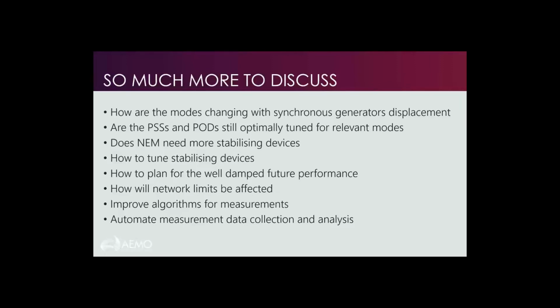On stabilizers again, can a reduction in inertia make the PSS less effective? It depends how they are tuned. If they are tuned for a network at a time with high inertia, and the inertia changes a lot, then yes, definitely, just by the nature of its tuning. If inertia reduces slightly, it may not, but I would think it would definitely change the nature of damping of that stabilizer.